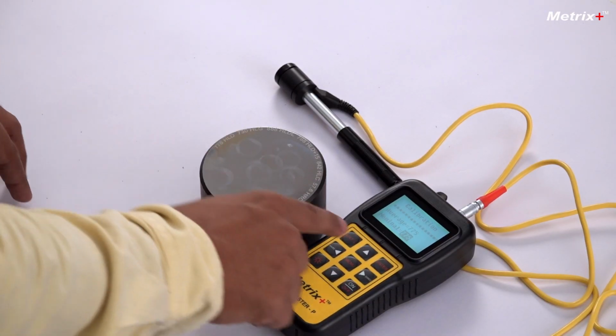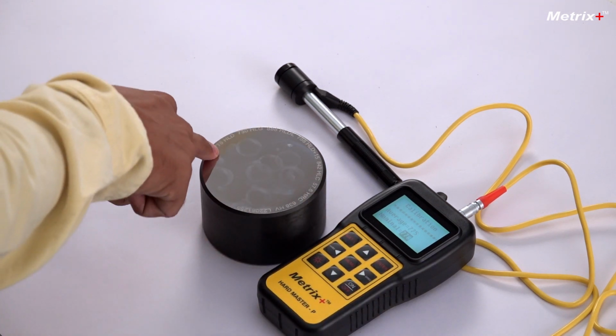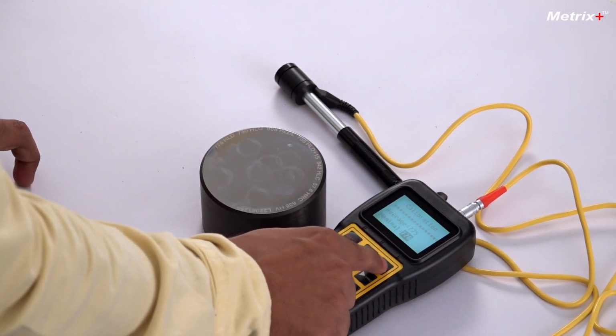Now, you can see the average value calculated is 775. This is in HLD because by default the unit is HLD. The nominal should be what is on the block. So the nominal is 778 as it is written on the block here. Once you do that, just press enter button and the instrument is calibrated now. Calibrate it from time to time if you see that the values are inaccurate.